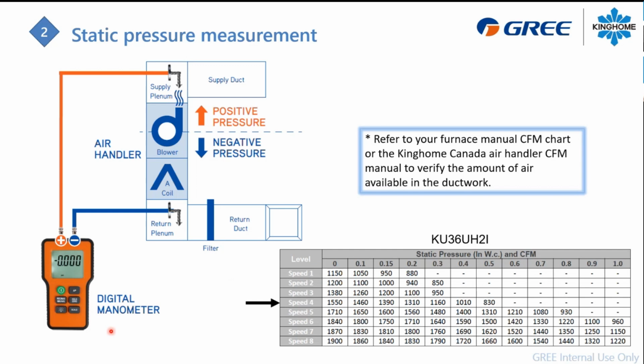So just be aware that you will need to use a digital manometer to find out what your static pressure is in both ductworks, so in the return duct and in the supply duct. You need to have both measurements to find the right number right here.